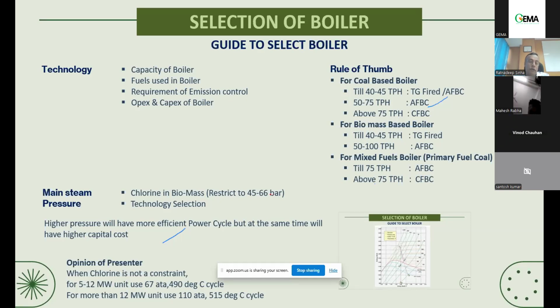And only you have to see, when you are using biomass, what is the chlorine content in the biomass, and that is important because if you go for a higher pressure with the chlorine content, there can be chlorine fouling in the superheater. So you have to restrict the pressure between 45 to 66 bar when there is moderate to high chlorine in the system.